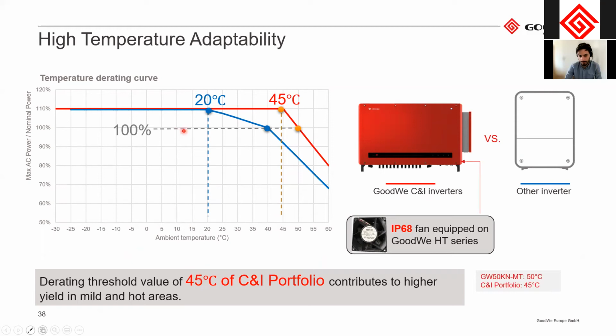So here you see a test between a competitor, the blue line, and our GoodWe MT inverter, the red one. Here you see the nominal power on the y-axis and the ambient temperature on the x-axis. As you see, for many inverter brands it's quite common now that they can have this 10% AC overload, so they could operate at 110% of the nominal power.